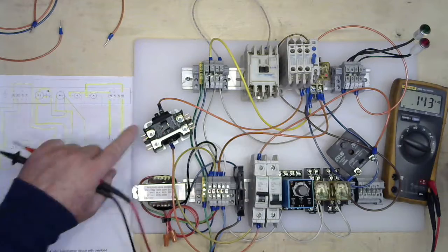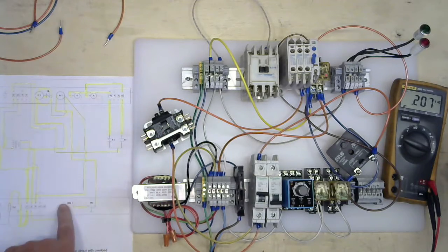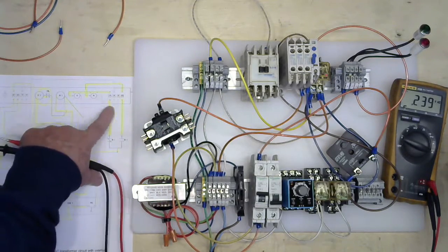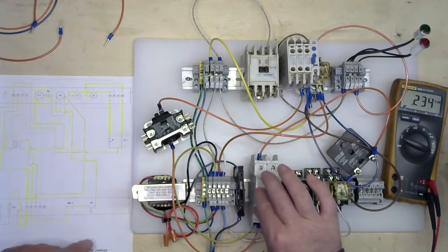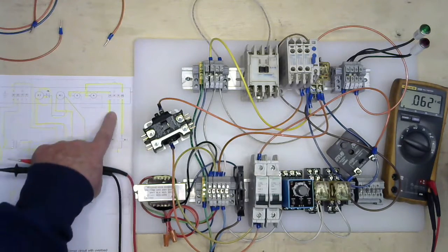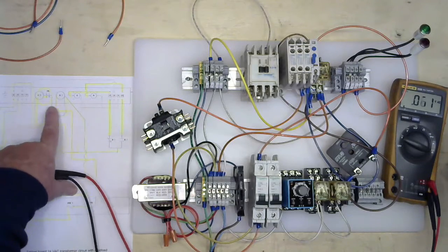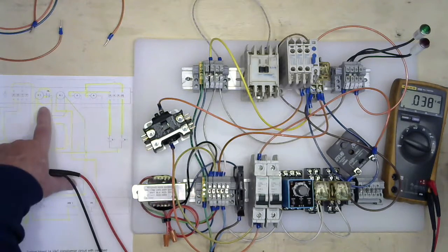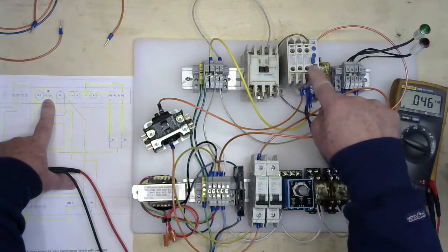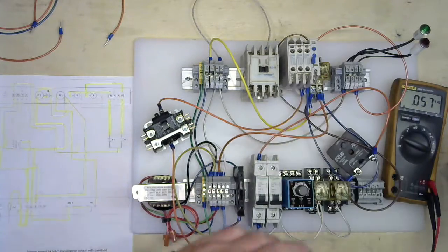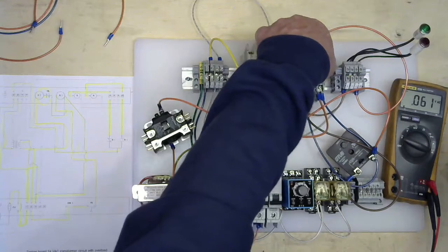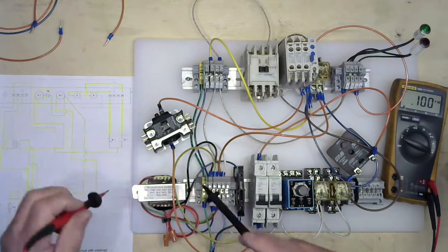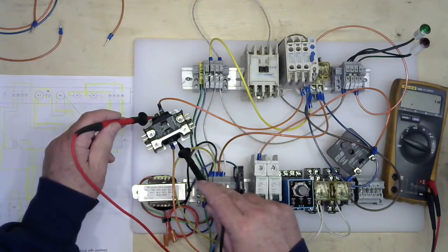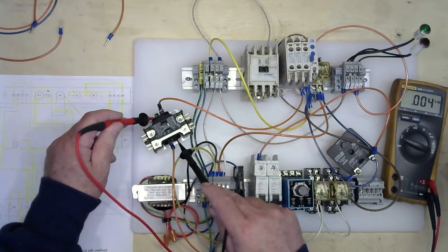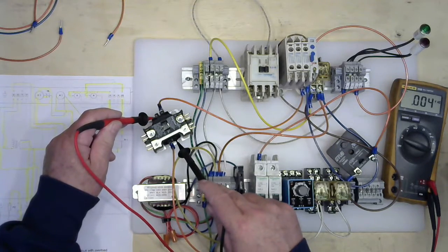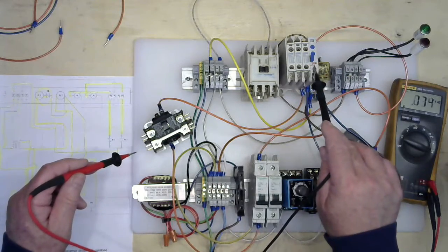Now let's test our relay. With our time delay, we know that this circuit works fine. We can turn that off. So we know this circuit here has nothing to do with our contactor. The only way we get our contactor to change state is to go through our overload. So we want to pull up on our overload. I'm going to go ahead and check my overload. I have 0 voltage across my coil because my overload is tripped.